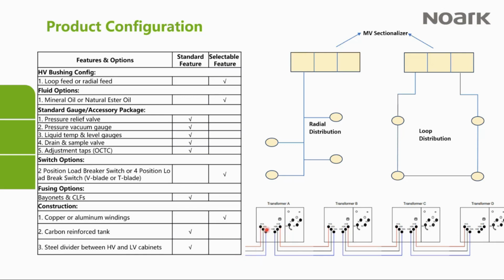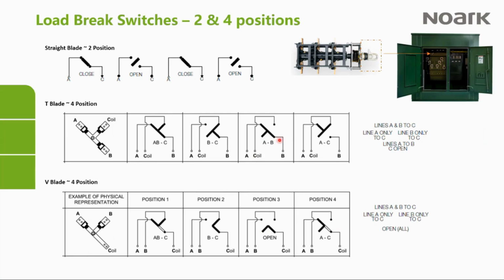And that's what we explained here with this diagram, because you can go from this bushing, it goes into the transformer itself, and then it leaves again through this bushing, you're going to the next transformer, and then again, you go from here to the next one. So that's what we call the loop distribution. So depending on what the customer wants, we can provide that, whether it's radial or loop distribution. Like I was saying before, these are the bushings that you have here. This will be the incoming and this is the outgoing, right? So it goes in from here into the transformer winding. At the same time, it is leaving the transformer through this other bushing. So if you see this, this is the loop type. If you see the radial type, it's just going to have three sets of bushings on this side.